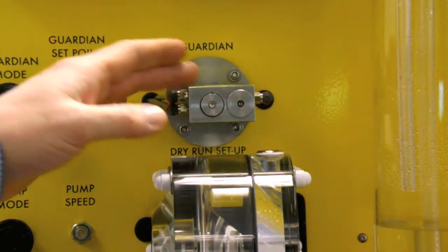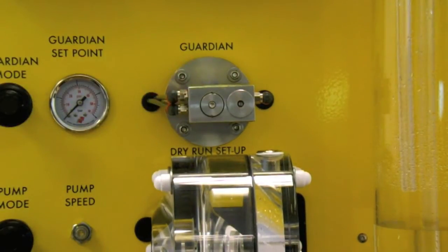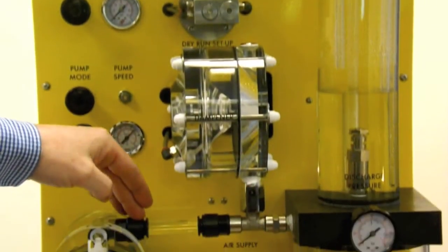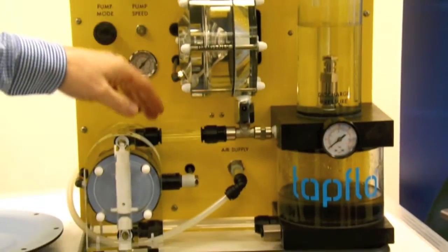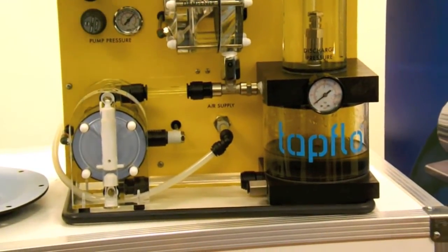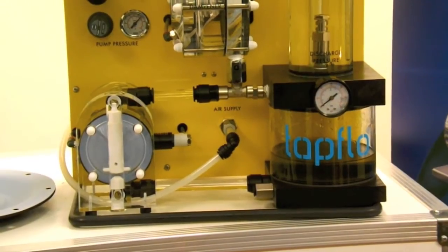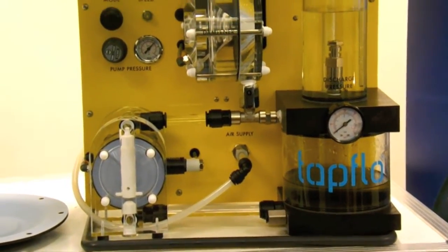Now the one we have set up here today is for dry run protection. So here what the guardian is doing is it is piped into the discharge line of the pump and it is monitoring the discharge pressure. So you can see here I have set the discharge pressure for the guardian to react at as 20 psi.